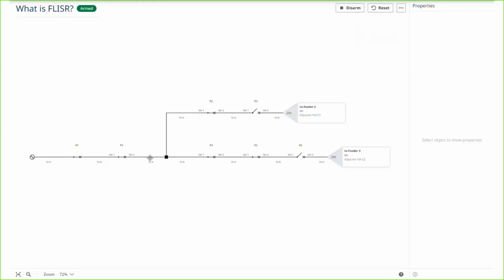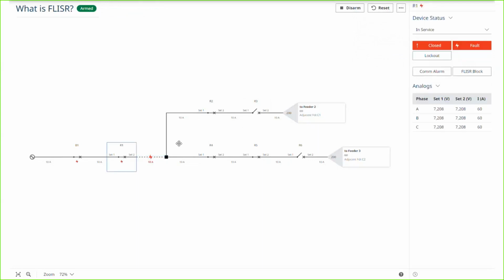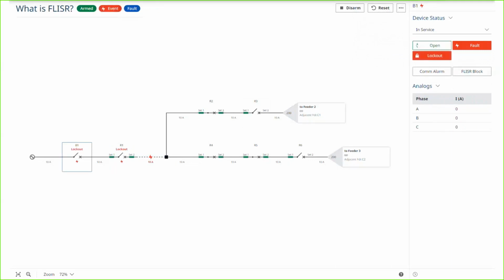Okay, so we've issued a return to normal control that's resulted in a sequence of controls being sent to reclosers that returns the circuit to normal. Let's do another example. So this is going to be another miscoordination, but in this case, both protective devices lock out. So breaker 1 locks out, recloser 1 locks out. What do? This is where it's important to follow the fault indications, regardless of who locks out.